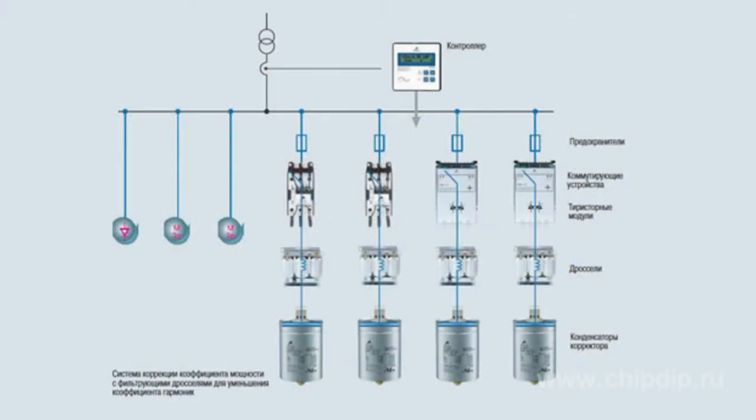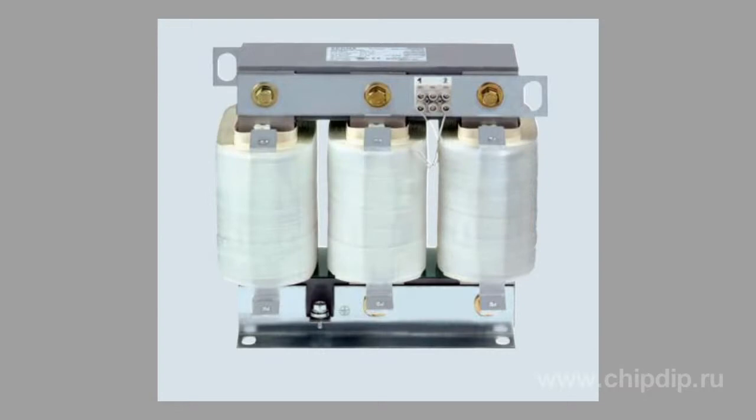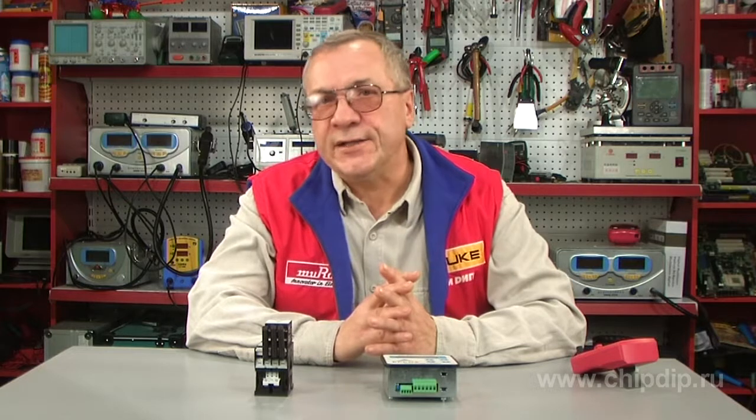Resonance effects can be avoided by connecting special filtering inductance in series with a capacitor. Detuned systems should be adjusted so that their own resonance frequency lies below the lowest voltage harmonics. At frequencies exceeding the resonance frequency, a detuned filter can serve as an inductance load for harmonics, while at 50 Hz it is a capacitance load only, allowing for power factor correction.